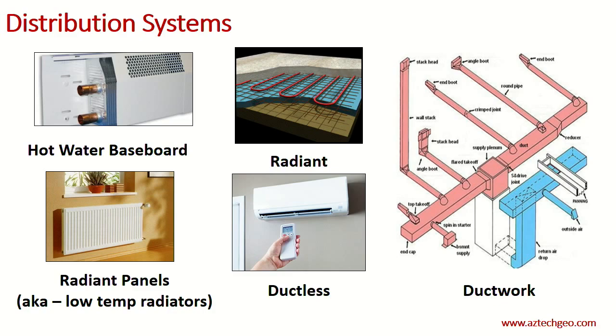So you can heat up water in either an air-to-water or water-to-water heat pump system and put it through a very high surface area radiator, sometimes called a radiant panel, or high efficiency baseboard. Instead of just a single tube with fins on it, you can have more surface area - often double - so you get more fin area, allowing a lower temperature water for a larger BTU output. We convert some single tube baseboard into higher efficiency so it can handle heat pump temperatures.